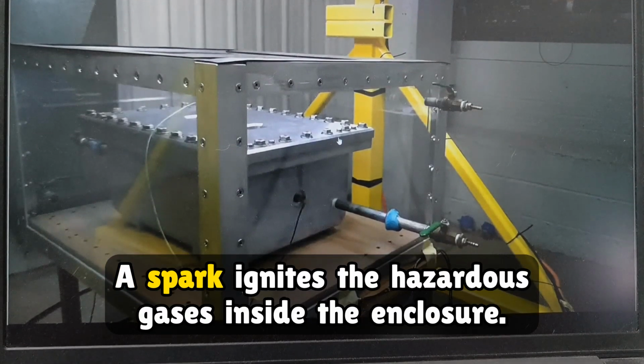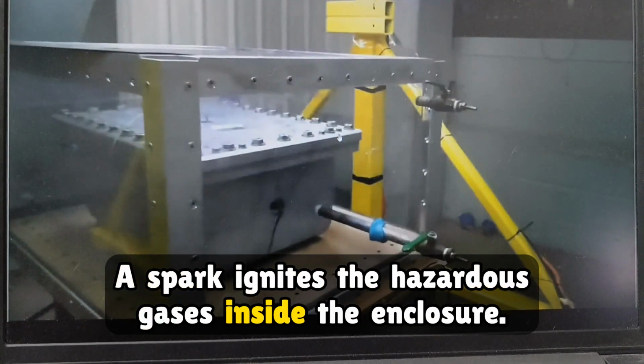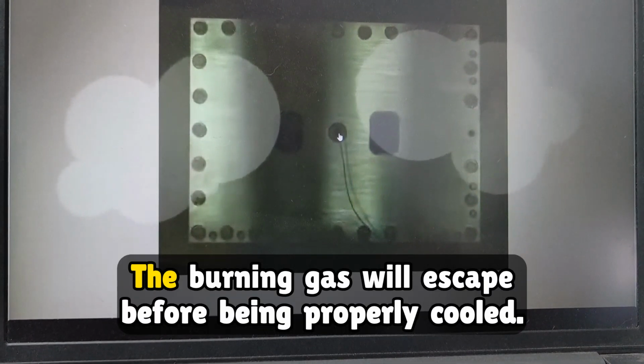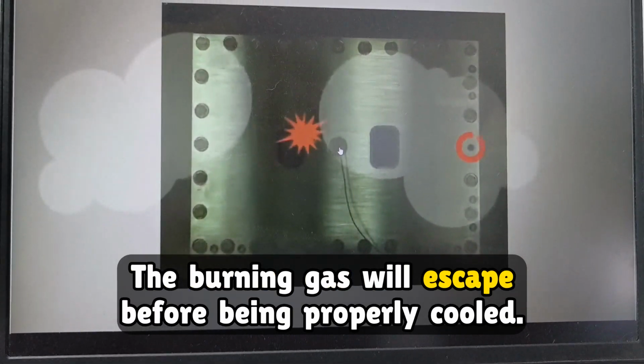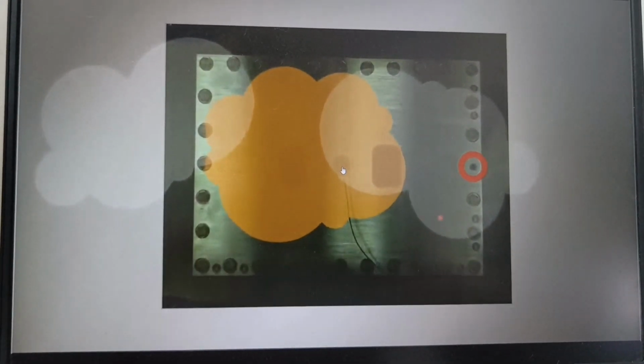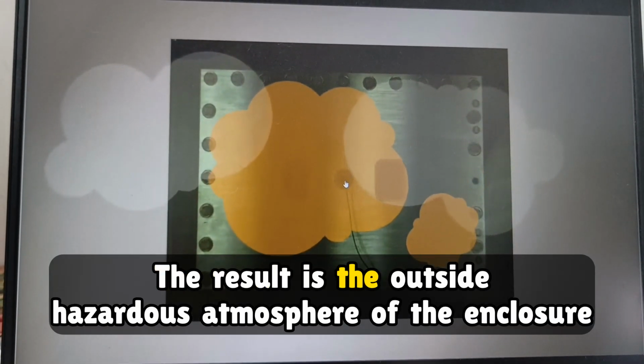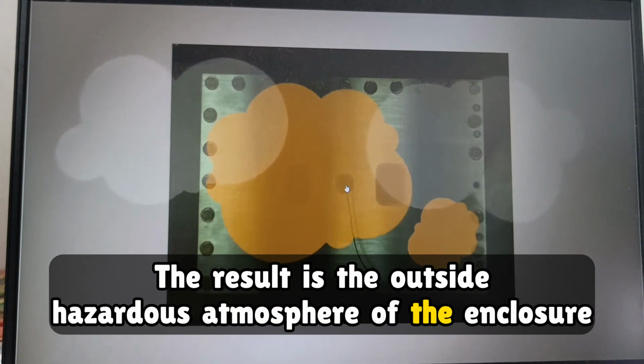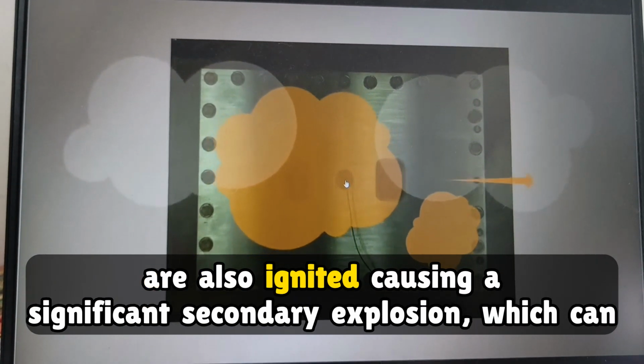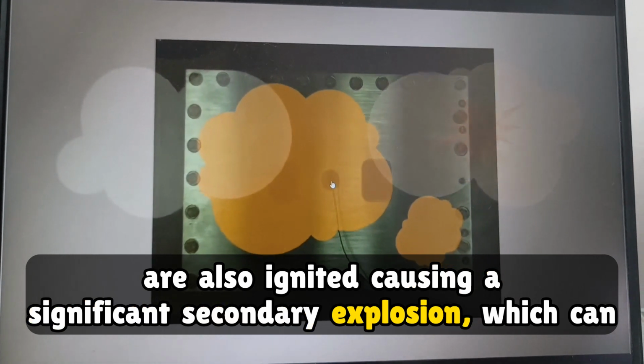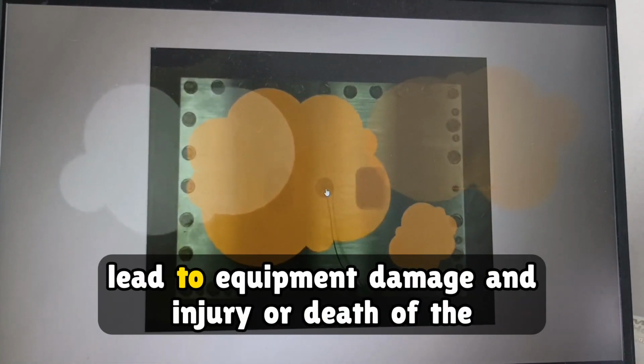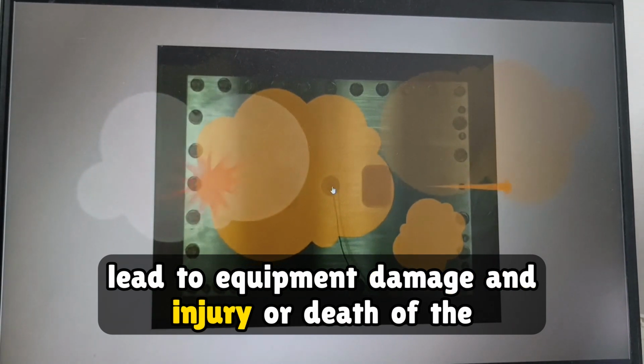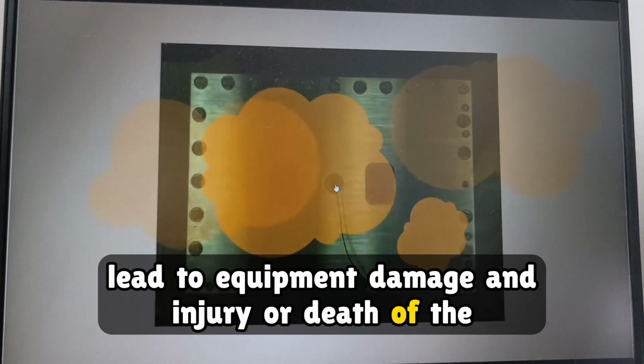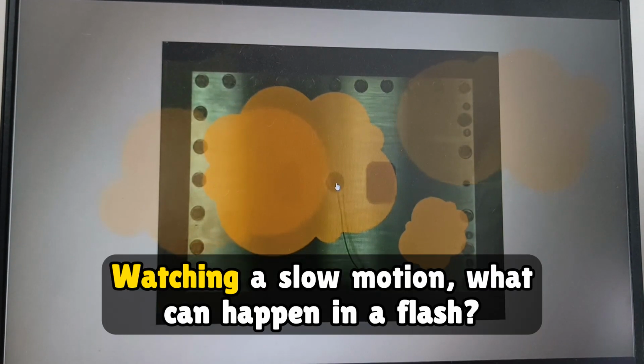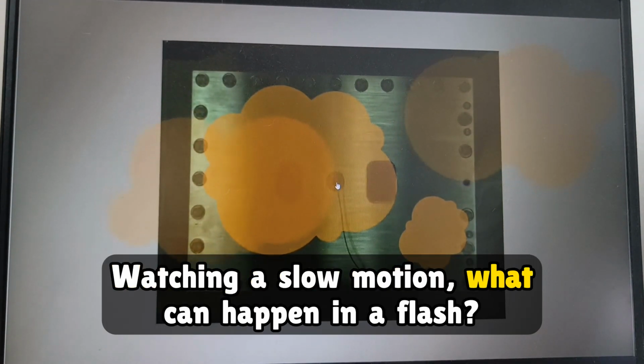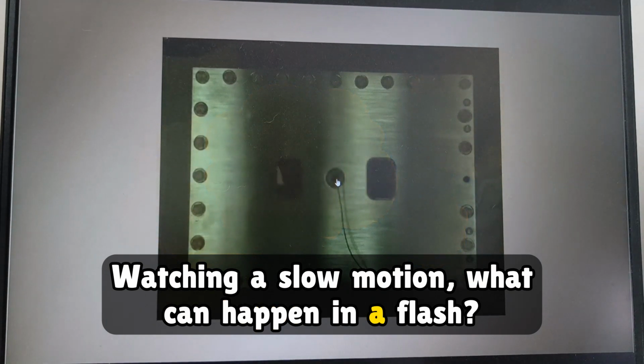A spark ignites the hazardous gases inside the enclosure. The burning gas will escape before being properly cooled. The result is the outside hazardous atmosphere of the enclosure is also ignited, causing a significant secondary explosion, which can lead to equipment damage and injury or death of the personnel. Watch in slow motion what can happen in a flash.